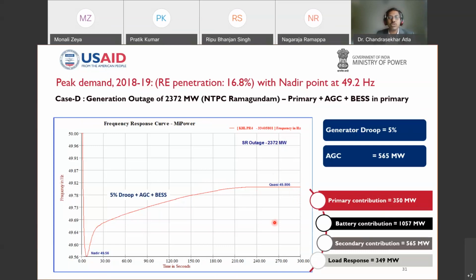Now referring to our 50 Hertz committee recommendation: for any big contingency in the system, the maximum possible nadir frequency should be more than 49.5, and quasi steady state 49.8. Taking these two limits, we defined the size of the battery required — about 1057 megawatt. We did a lot of simulation studies by varying the battery size, and finally settled on this value of 1057. This is the battery capacity required for the future 21-22 condition, in case you want to minimize the burden on conventional units to participate in primary reserves.